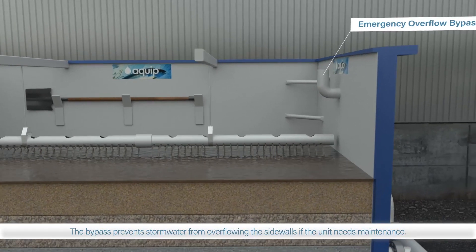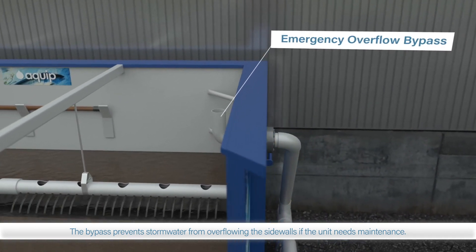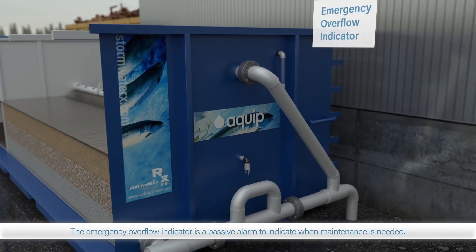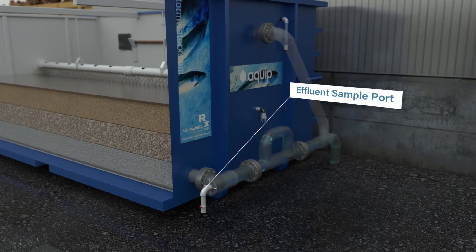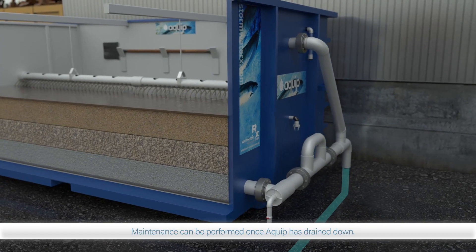Aquip has several important features: the emergency overflow bypass prevents flooding if the filter is not properly maintained; the emergency overflow indicator serves as a passive alarm to indicate maintenance is needed; and the adjustable head control enables optimal process hydraulics.